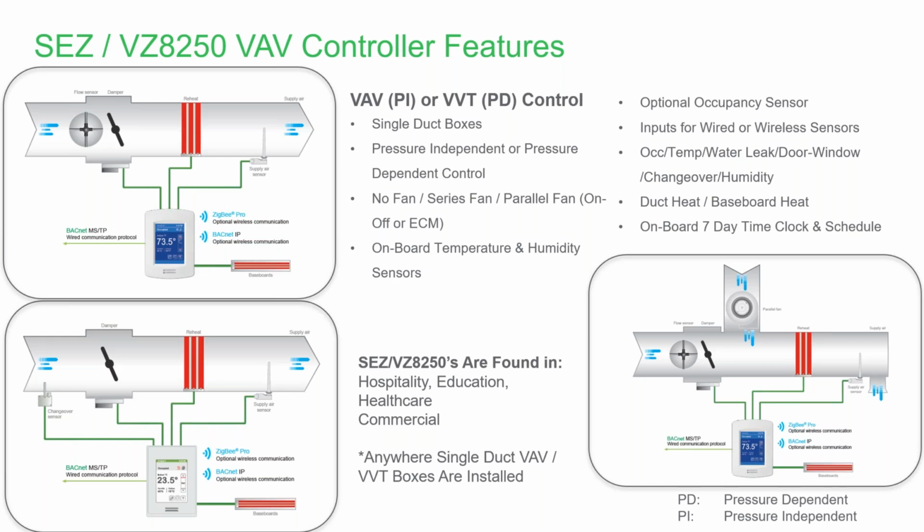One thing that we're seeing coming out of the field in applications where there's VVT systems, and there's hundreds of thousands, if not millions of these products that are out in the world today that have been running for 20, 30 plus years, that still have a laptop sitting in a mechanical room plugged into a panel that's running DOS. And that's how you get into your VVT system and look at it. And those systems are failing. Whether you know it or not, they're failing. This particular product is a prime candidate for a direct replacement for those applications.